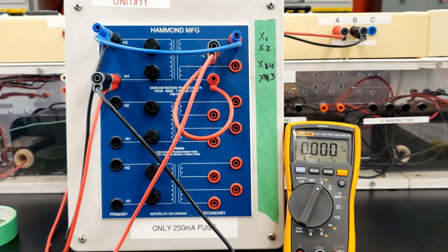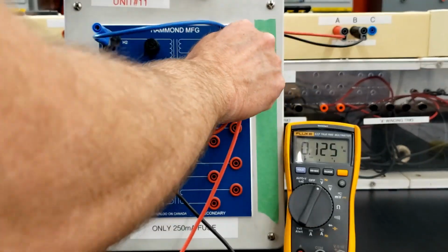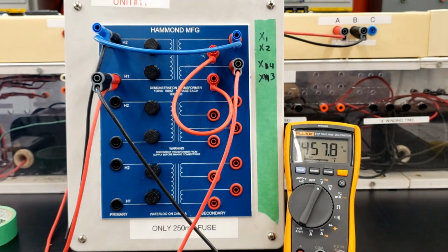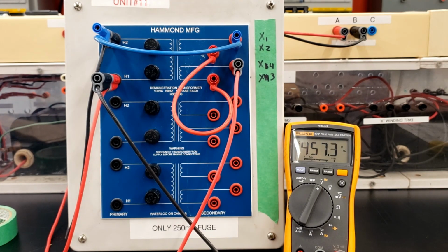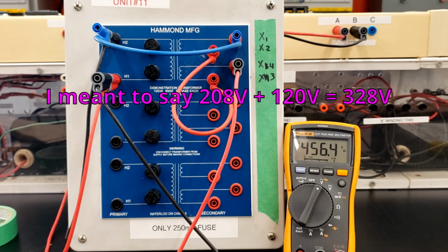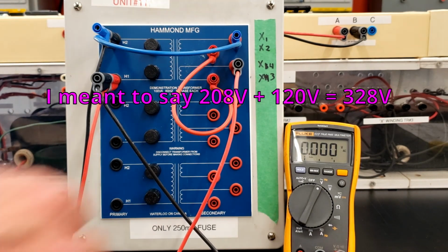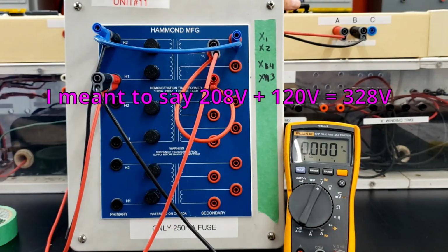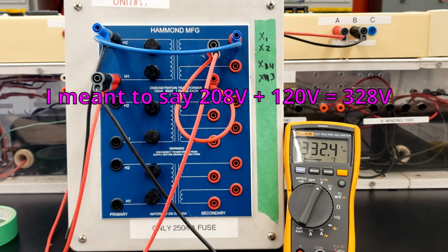The voltage that we saw before was 460 volts. We were thinking 240 plus 208, so we were thinking it'd be 448. We're seeing a little bit larger voltage there. The voltage between the primary and one winding should be 240 plus 120, which should give us around 360 volts. So I'm going between H1 and X2, and we'll see what that voltage is. There we go, 330 volts. I was expecting 360, so a little bit less voltage there.